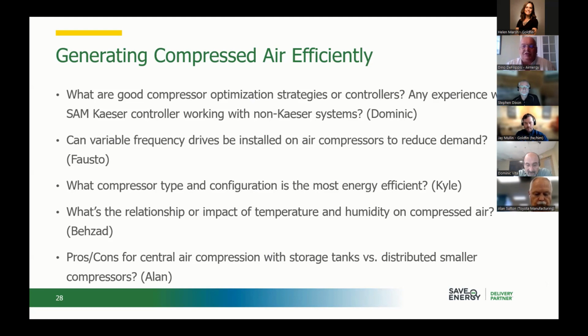I would say that managing multiple VFDs becomes a major issue. There's that control gap you're going to find where they don't fight each other, and which one is going to load first, then unload, then trim with multiple compressors. If they're in the same room or they're satellite compressors, it does become an issue. You're probably almost better off saying, I'm going to use these VFDs flat out, full load as fixed, and then trim with the other VFDs. There isn't a controller out there that could properly manage multiple VFDs, especially 6 of them.